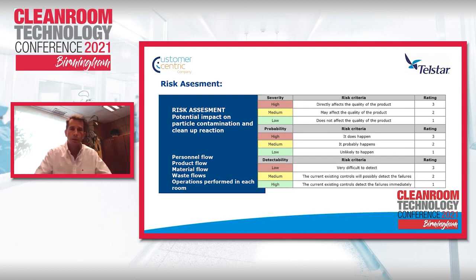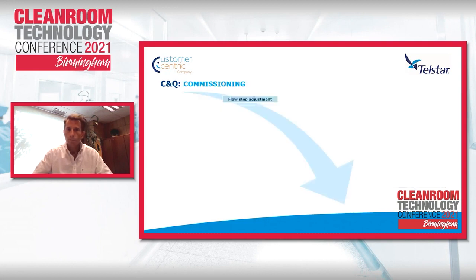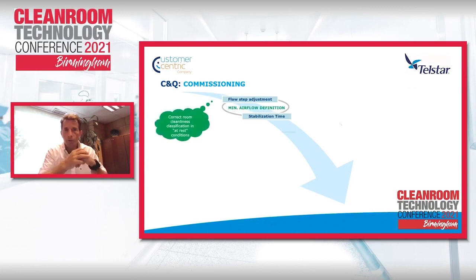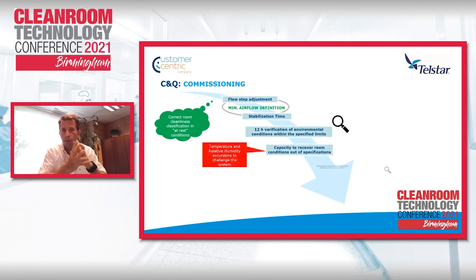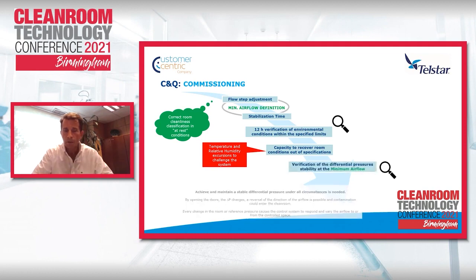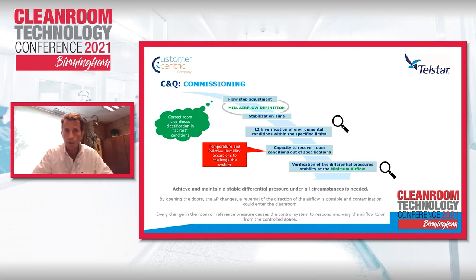But we are providing, let's say, a solution that can reduce the operating cost. So how do we qualify this? Do we qualify it with conventional criteria, or shall we qualify it at the minimum flow rate? Well, first, as I said before, we have this commissioning phase where all these parameters, although we have the initial data from the engineering, are confirmed during the practical commissioning.